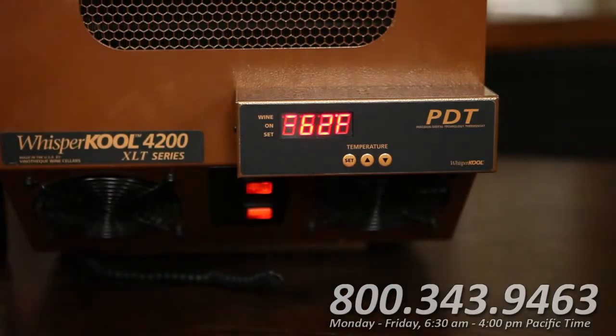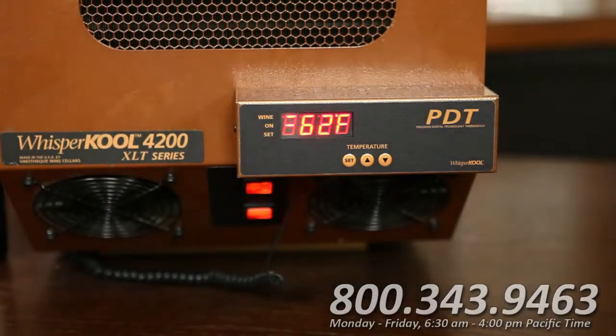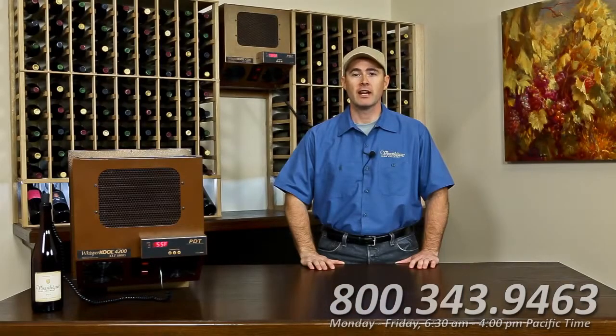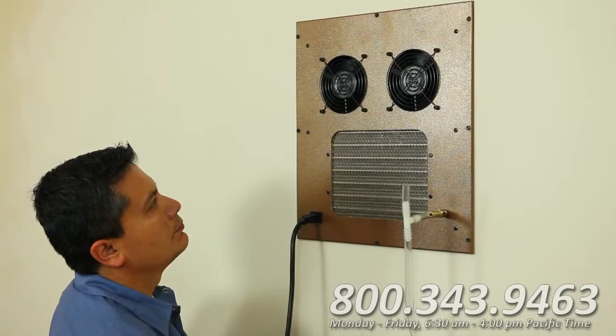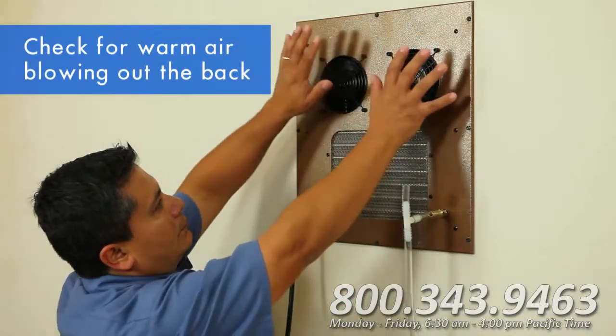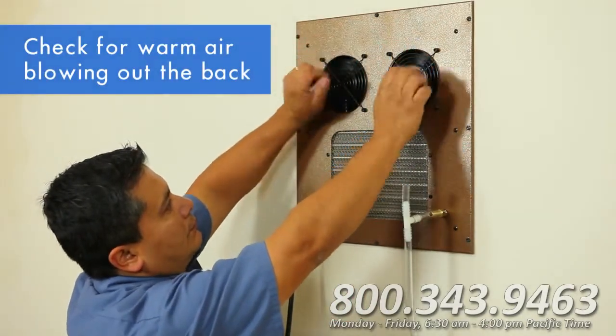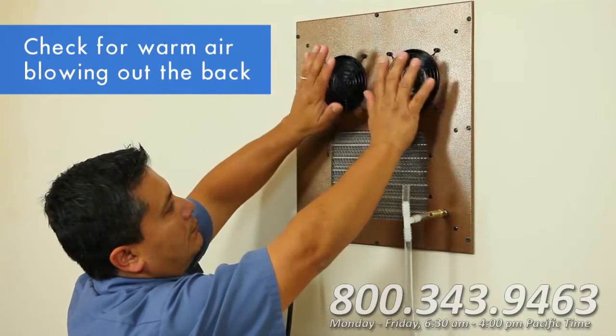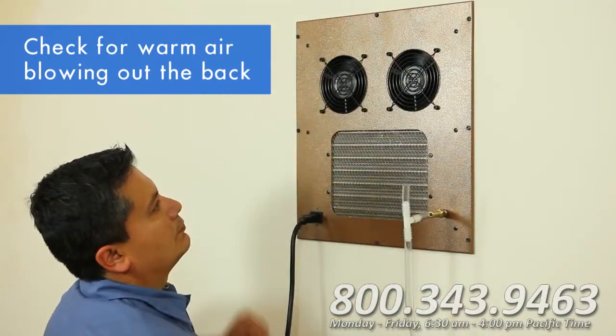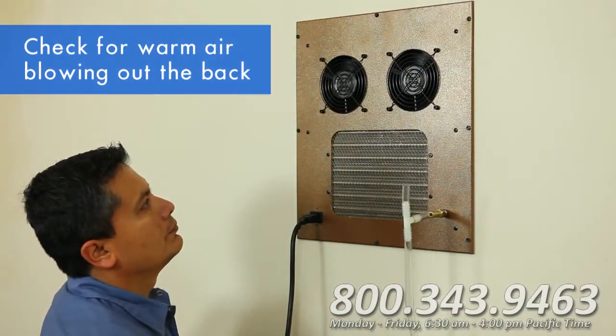Because the unit will only run for a maximum of 90 minutes at a time. If there is no countdown, or if the unit does not turn off at the end of the countdown, then you have a thermostat problem. Also, check to see if all of the fans are blowing and if they appear to be turning at the same speed. The best way to know if your unit is working is if heat is exhausting out the back side. If you feel warm air blowing out the back, your unit is functioning properly, and you need to consider any installation and ventilation issues.